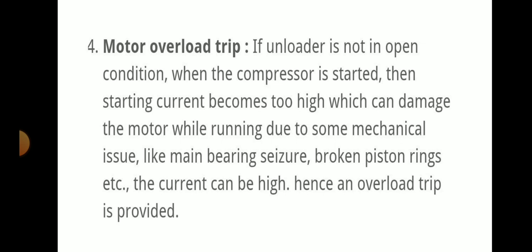If the unloader is not in the open condition when the compressor is started, the starting current becomes too high, which can damage the motor. While running, due to mechanical issues like main bearing seizure or a broken piston ring, the current can be high, hence an overload trip is provided.